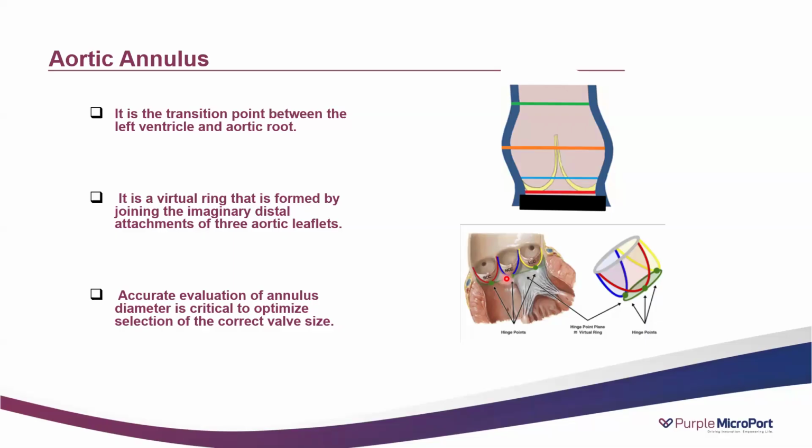Because the more effective orifice area we get, the more durability of the valve will come. So, anyways, that is a different subject. As of now, in the interest of the audience, I'm telling you the annulus corresponds to your valve size.